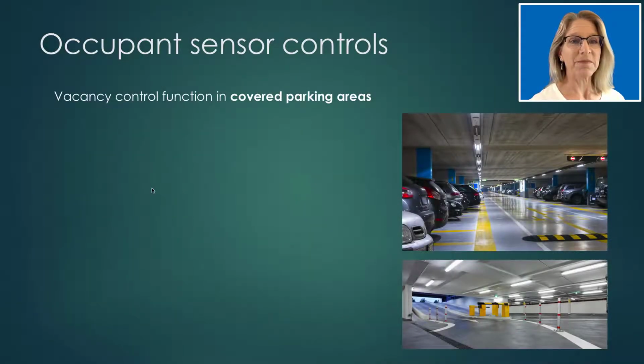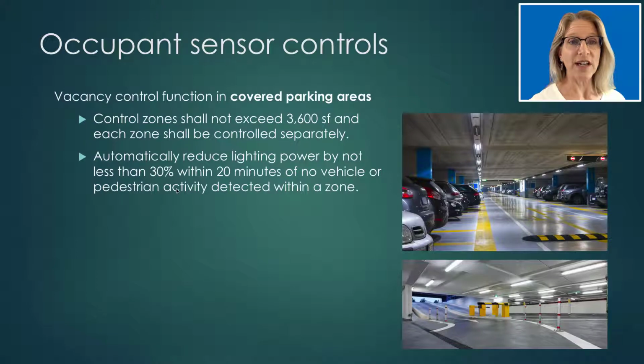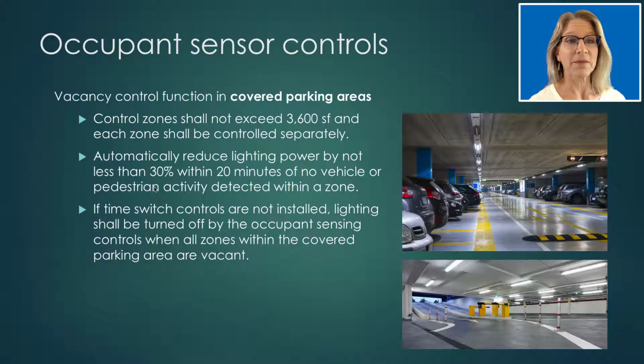integrated. For covered parking areas, the control zones shall not exceed 3,600 square feet, and each zone shall be controlled separately. The controls shall automatically reduce the lighting power by not less than 30% within 20 minutes of no vehicles or pedestrian activity being detected within that zone. If time switch controls are not installed, then the lighting shall be turned off by the occupancy sensing controls when all of the zones within the covered parking area have been vacated.